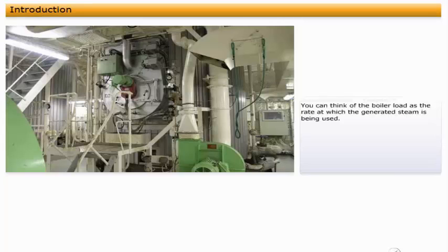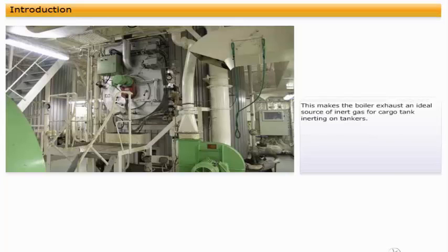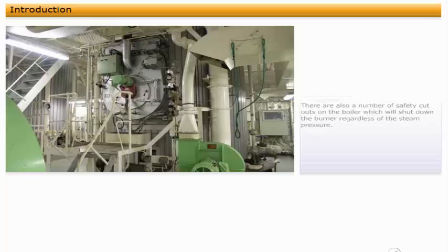You can think of the boiler load as the rate at which the generated steam is being used. Also, unlike the diesel engine, boiler combustion takes place with only a small excess of air, so that there is little unused oxygen, often less than 5% in the boiler exhaust. This makes the boiler exhaust an ideal source of inert gas for cargo tank inerting on tankers.